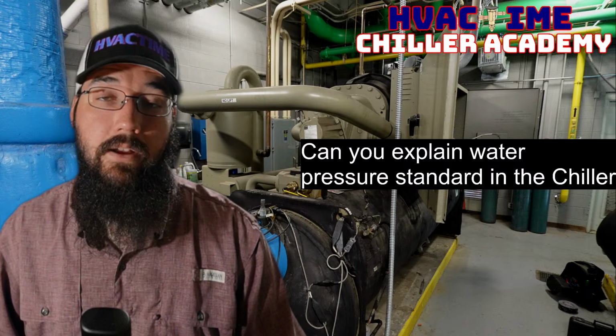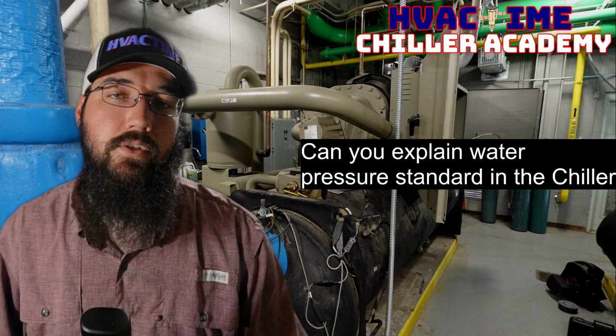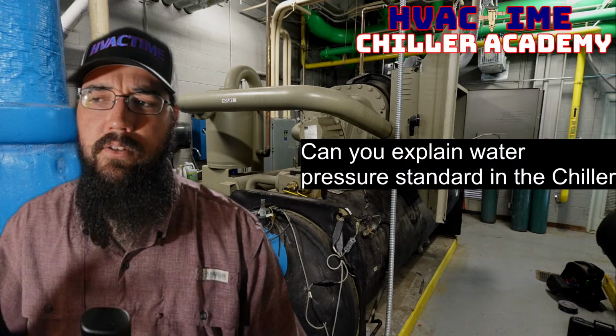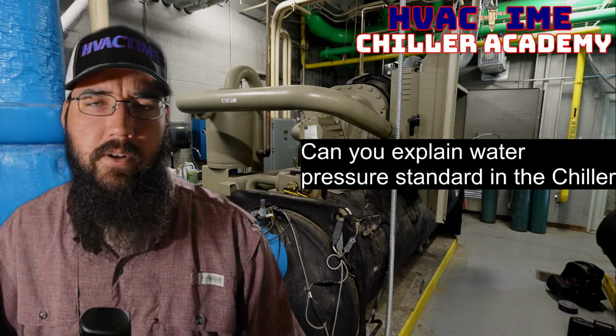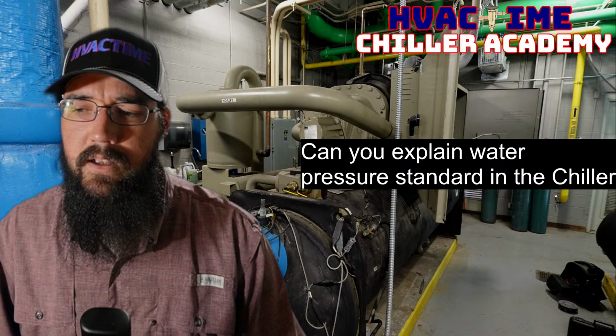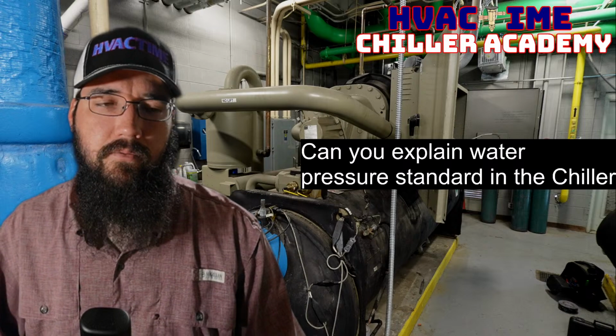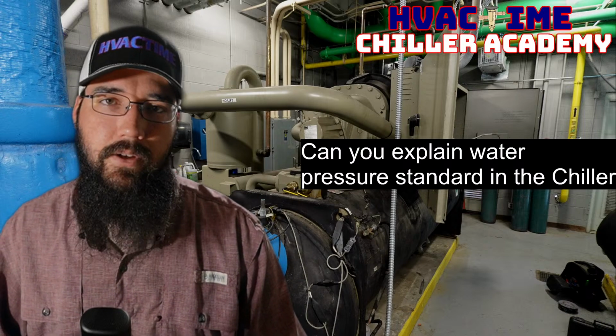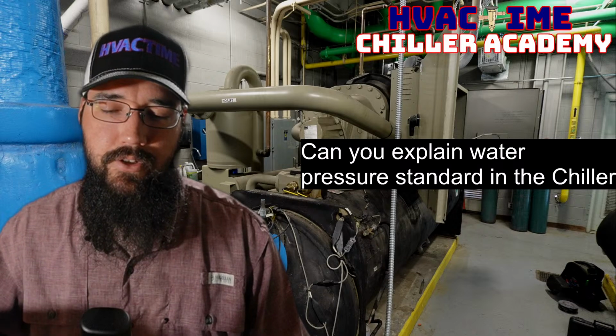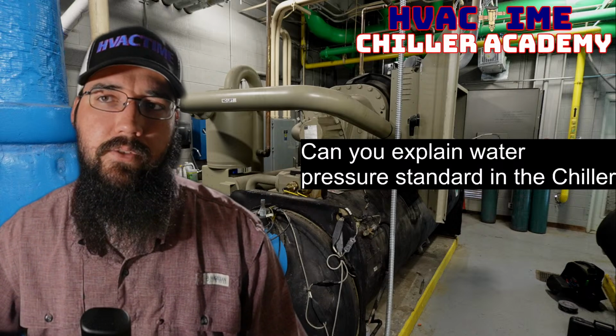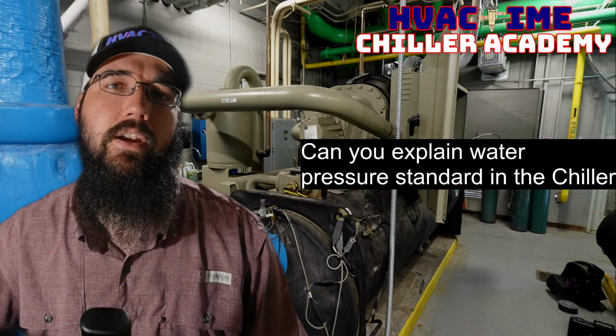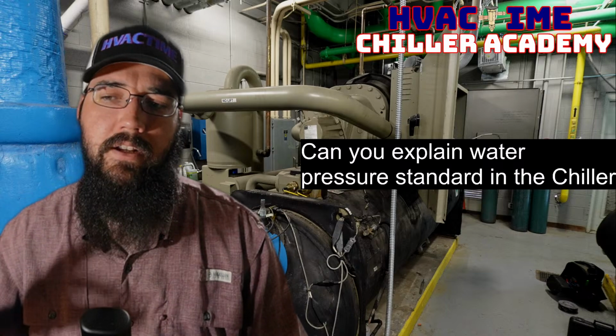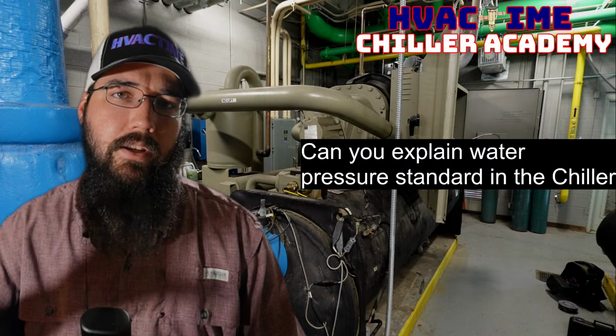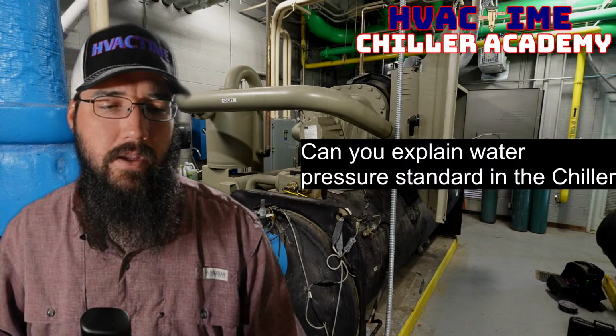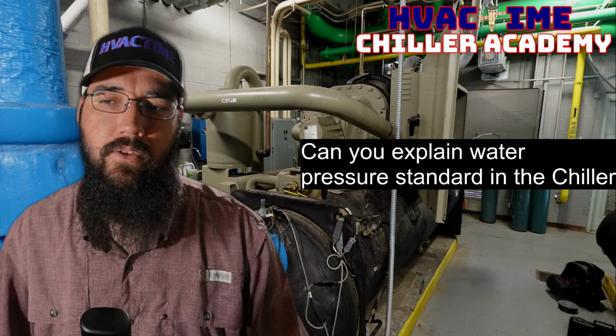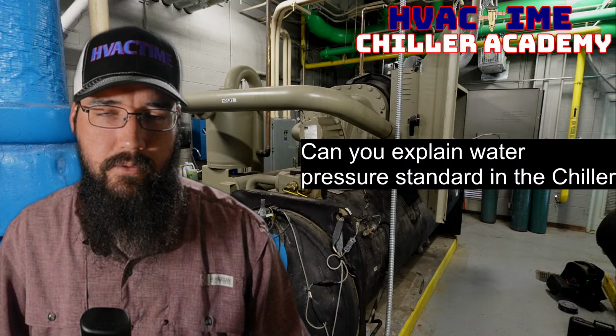I hear all the time, you ask, well, what's your loop pressure need to be in that plant? Oh, I mean, loops are supposed to be 35 psi or whatever. And that's just, no, you have to take into account your elevation changes. That elevation is going to change your head pressure, in addition to just where the pumps and equipment are located inside of that loop. That has everything to do with what pressures and such you actually require.